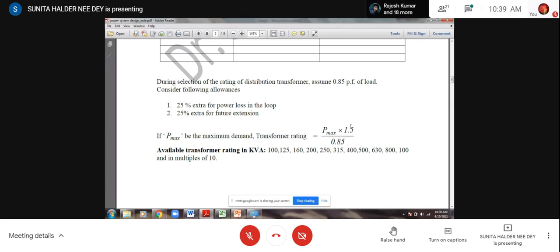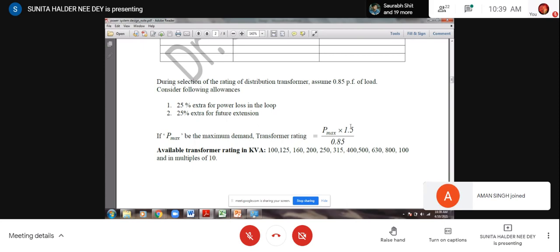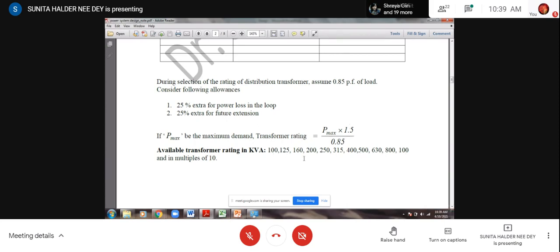All of you, can you? Now, the transformer rating you calculate may be a theoretical one and may not be possible physically, because transformer manufacturers design the transformer for a specified voltage level and defined kVA. So these are the available transformer ratings, shown up to 100, 800 only, then multiples of 10. Say if your required transformer rating comes to 1350 kVA, you will not get it. You can get 1250 kVA or 1600 kVA.